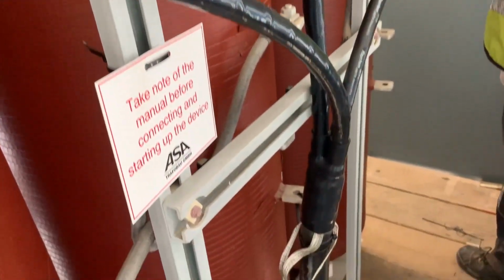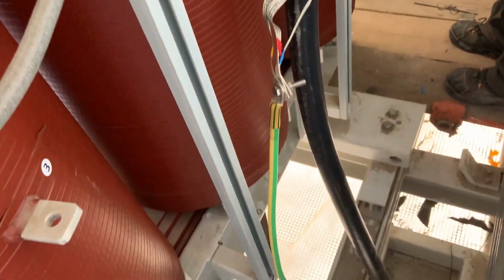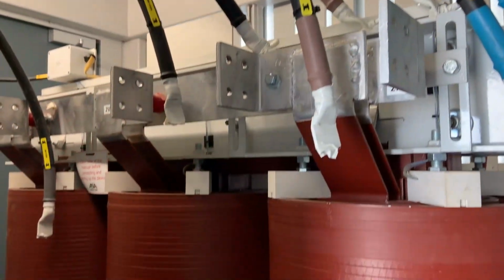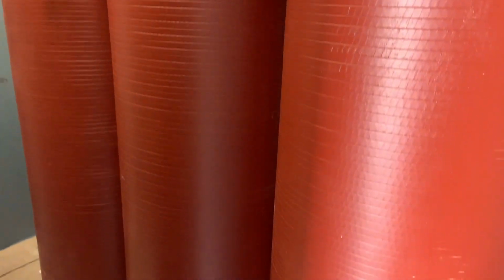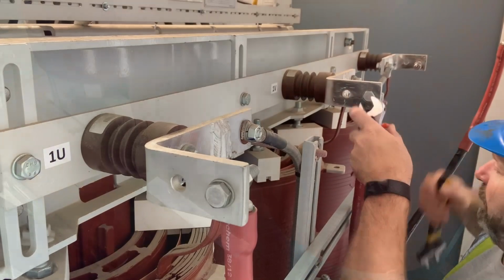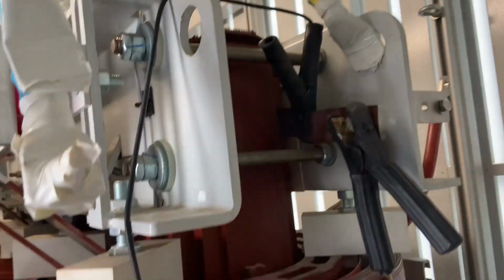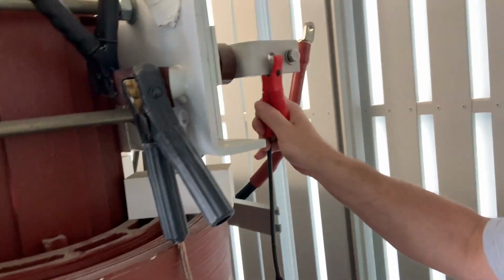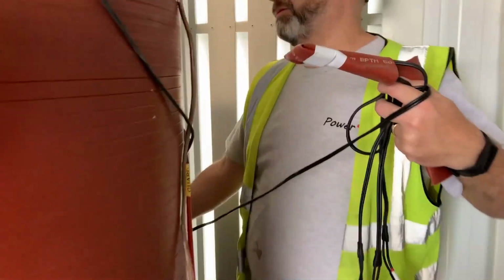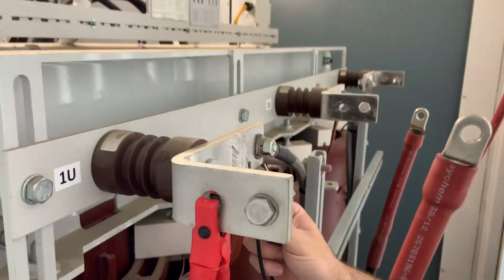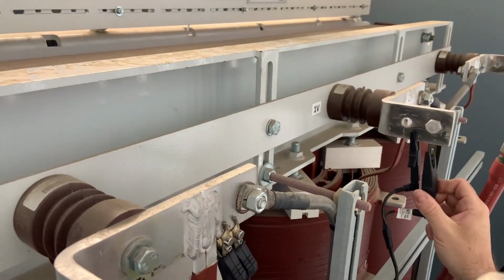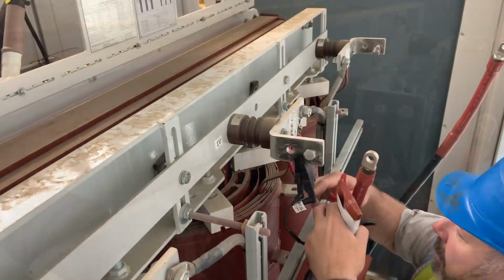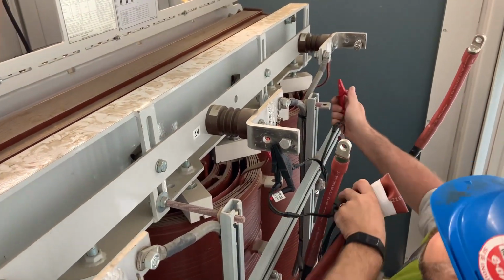This side shows the 3.3 kV supply cable, and this is the LV side of the transformer where the LV cables have been disconnected. The connections we want to make are between the core of the transformer, the framework, and the high voltage connection onto 1U on the HV winding. We then link this across to 1V and 1W connections on the high voltage.